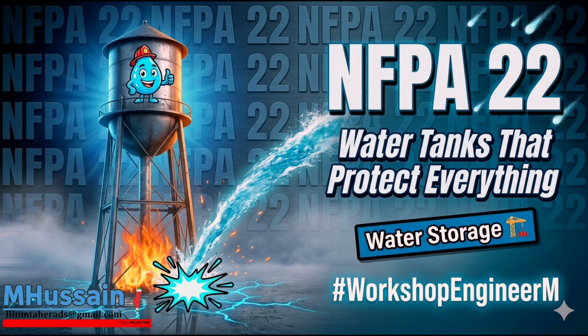And crucially, you have the vapor pressure of water. If you ask a fire truck to draft water from a depth greater than 15 feet, the vacuum required becomes so deep that it drops below the vapor pressure of the water at ambient temperature. The water inside the suction hose will literally boil into vapor without any heat being applied, and the pump will cavitate on the vapor it just created, which destroys the pump, like we talked about earlier.